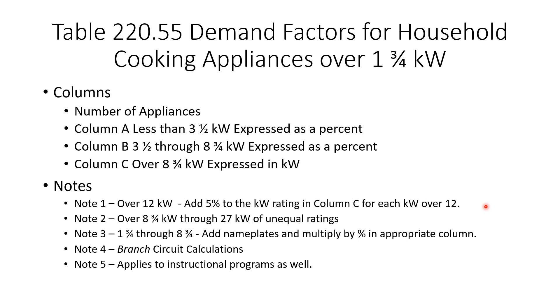For example, say you have one 14-kilowatt appliance. One appliance in Column C gives you 8 kilowatts off the table. Since it's 14 kilowatts — two kilowatts over 12 — you increase the 8 by 10 percent (2 × 5%). So 8 plus 10% equals 8.8 kilowatts.